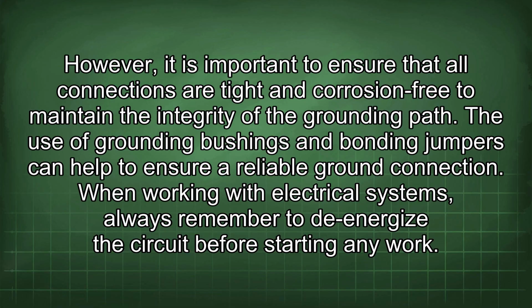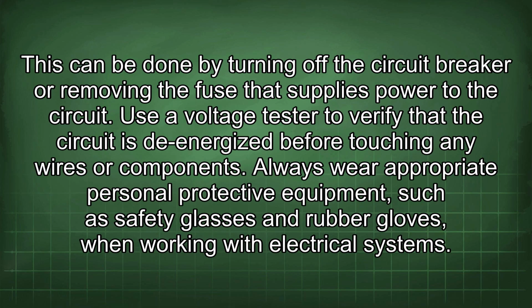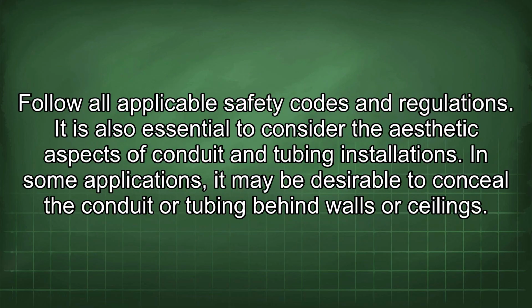When working with electrical systems, always remember to de-energize the circuit before starting any work. This can be done by turning off the circuit breaker or removing the fuse that supplies power to the circuit. Use a voltage tester to verify that the circuit is de-energized before touching any wires or components. Always wear appropriate personal protective equipment, such as safety glasses and rubber gloves, when working with electrical systems. Follow all applicable safety codes and regulations.